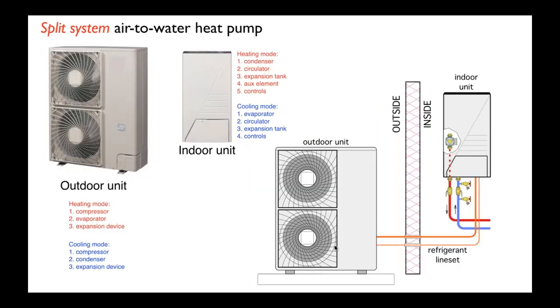Now, the other type of system is a split system. And this is more typical of what a central air-to-air heat pump or central air conditioning system would have. We have an outdoor unit. Oftentimes, it's called the condenser, especially in an AC system, an air conditioning system, because it's where the heat from cooling the building is being dissipated. But it also, in a heat pump, functions as the evaporator in the heating mode of operation. Now, we have refrigerant lines that come in from the outdoor unit, and they go to an indoor unit, and the indoor unit has the refrigerant-to-water heat exchanger.